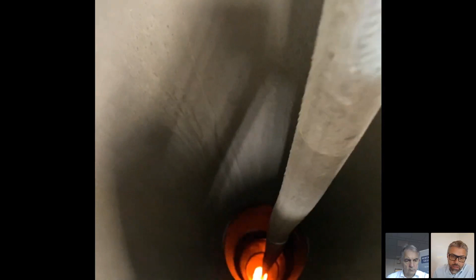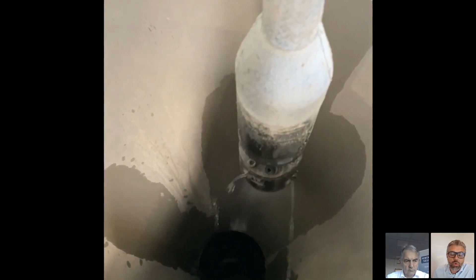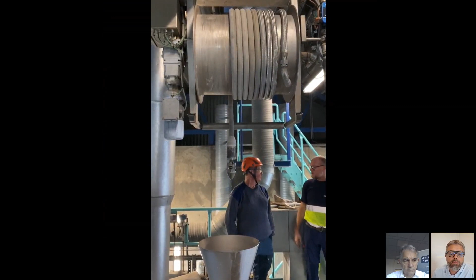As you can see, when it's coming out of the furnace, there's still a small amount of water running, because we need to keep the nozzle head cool all the time, as it's going into this harsh environment. The water is the medium for cooling and also the cleaning medium. Then it goes back up into park position, ready for the next hole you want to clean.